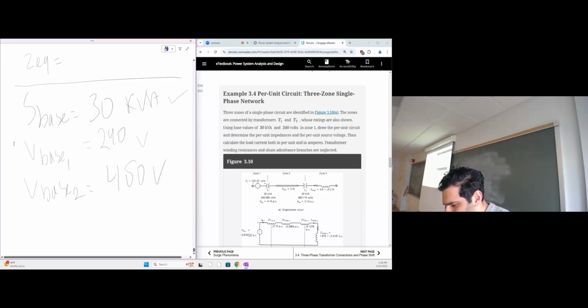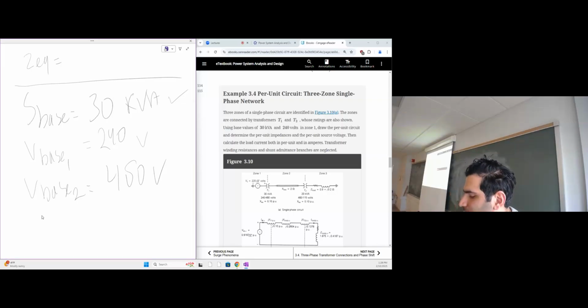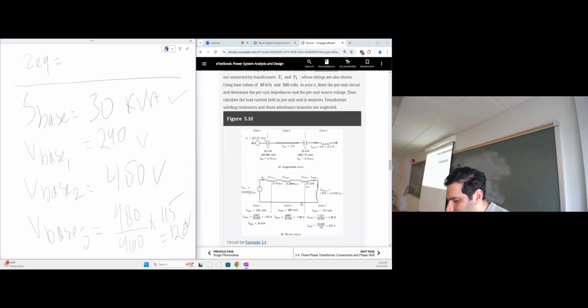No. You are here on zone 2. It's 480, but the transformer rating is 460, not 480. So it should be higher. V base 3 would be 480 over 460 times 115, which should be like 120 maybe. You need to check the ratings here. You were here at 480, but this transformer rating is 460. You cannot put 115 for zone 3. It will be higher because we are moving forward.